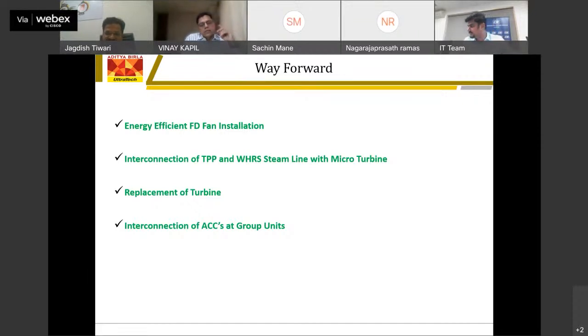For that, we have taken capex and projects, sir. We have taken capex for an energy efficient forced draft fan installation in the boiler, and we have also done the designing of one new project, for connecting the TPP steam line with the WHRS steam line. In between, we are installing a micro turbine. Instead of a PRDS, we are not going to install the PRDS; we are going to install the micro turbine that will reduce the pressure and temperature of the steam, and that lower pressure and temperature steam we can directly feed to the WHRS line, sir.